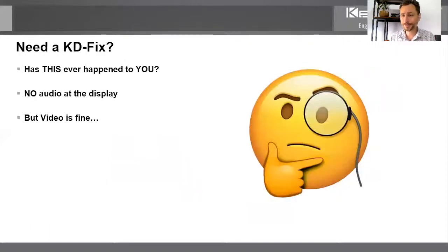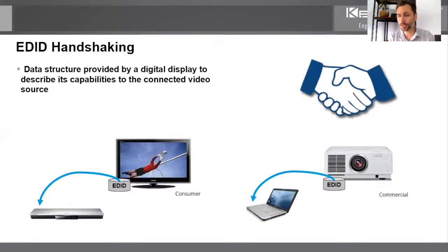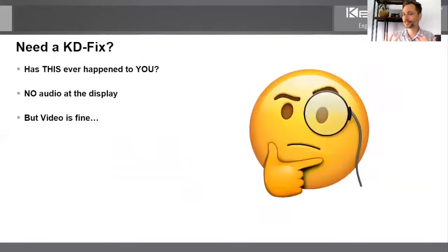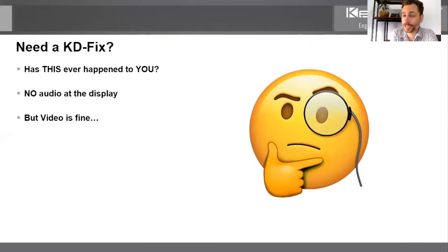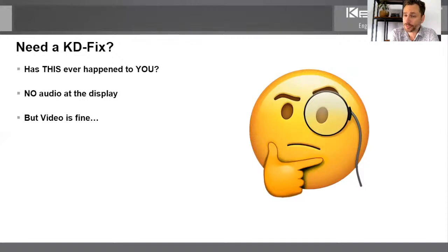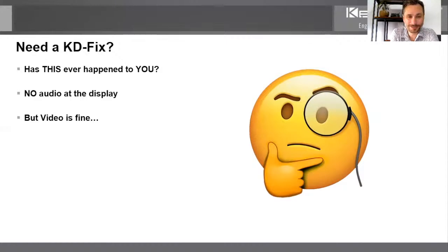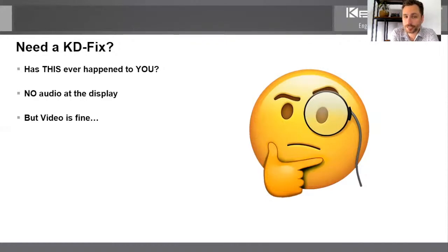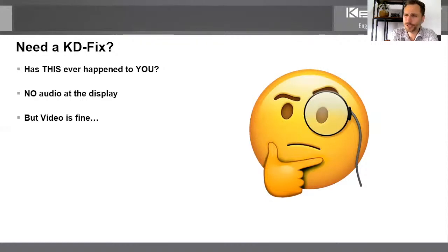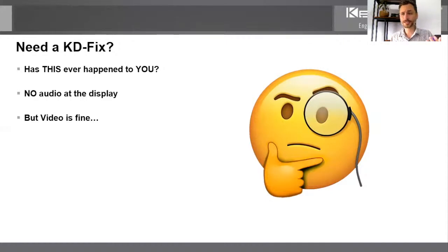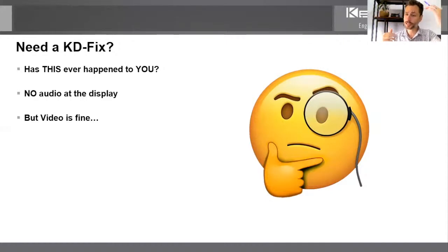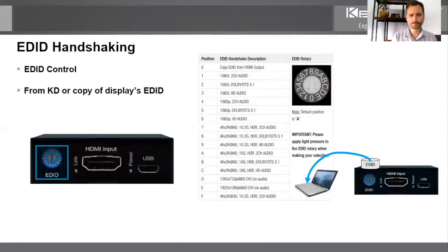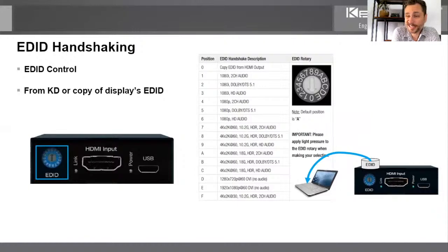So the handshake goes backward from the display to the source. And it seems easy when you have one to one. But that's not the world that you do your business in. That's not the world that Key Digital does our business in. And it's not the world that your clients have hired you to work in. So here's an example of a failed EDID handshaking. Your video is fine at the display, but you don't have any audio. Because the handshake is not just the video. Remember, it's the video resolution and the audio format as well.